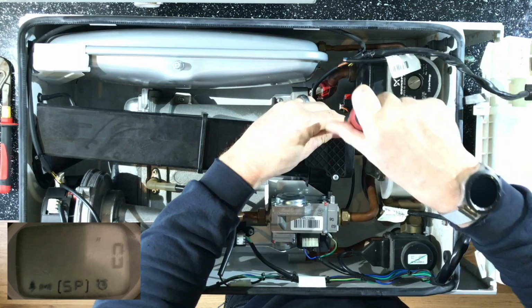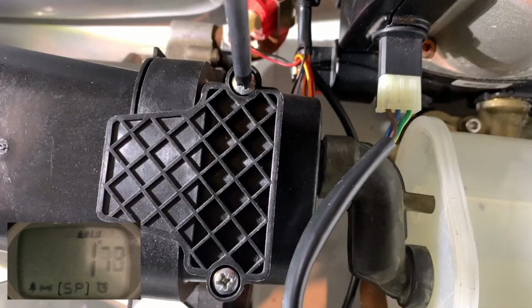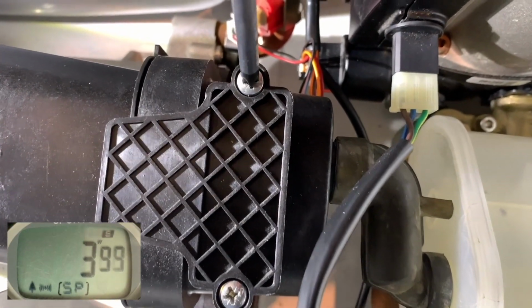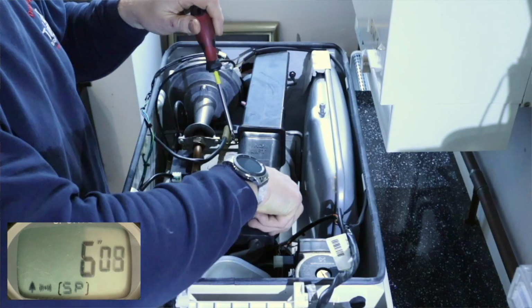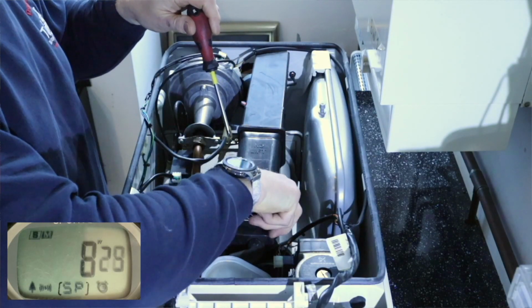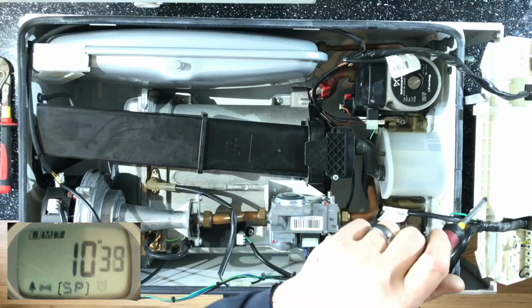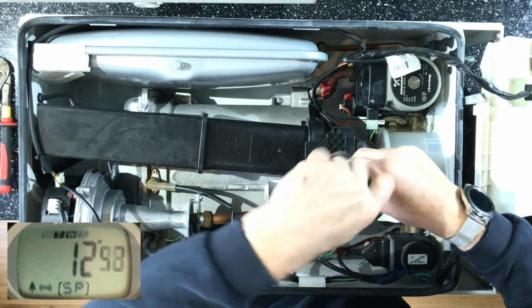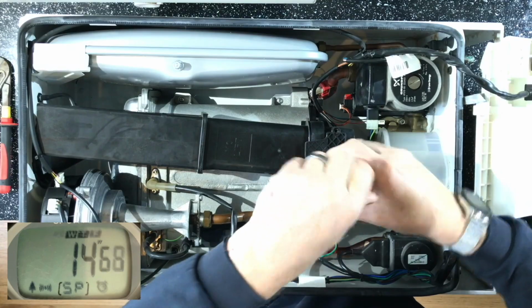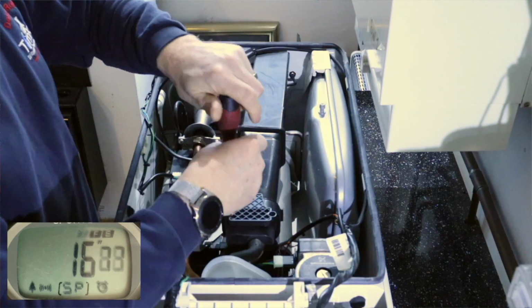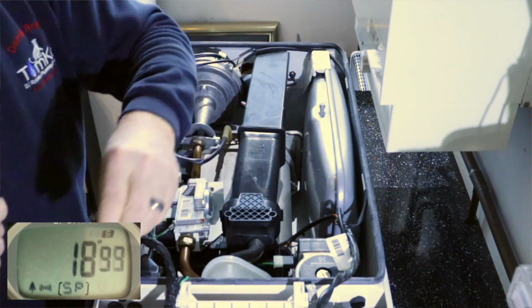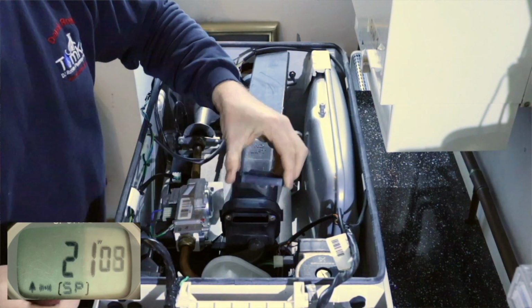Now, the first thing I'm removing are these two screws, and these two screws hold the sump cover on. What the sump cover does is allow you access into the sump when you come to service, but it also holds the flue manifold, which connects the sump to the turret, in position, and you have to remove this cover when you want to remove the flue manifold.